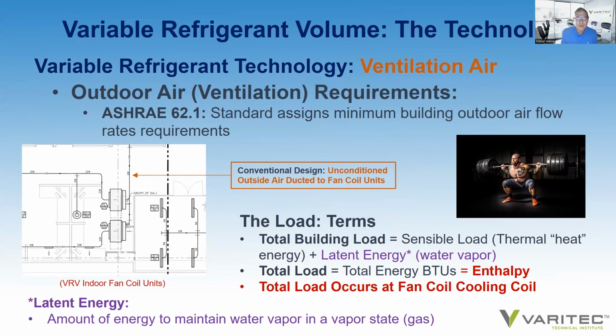So what about the ventilation air that we require to maintain a healthier environment? How do we deal with ventilation air and the outdoor air necessary for a variable refrigerant system? A conventional approach, certainly in Phoenix, Arizona, is to apply an outside air duct and tie it into the return air section of an indoor air handler, either a ducted unit or even into ceiling cassettes, so the system draws the outside air into the space necessary to meet the ventilation load.